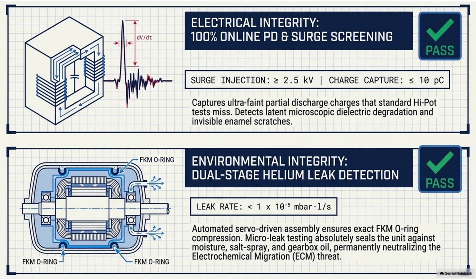By the time that wave reaches the motor terminals, the filter has squashed the violent vertical spike into a gentle slope, bringing the dVdt stress down from 10 kilovolts per microsecond to under 1.5 kilovolts per microsecond. It is like putting a massive shock absorber between a sledgehammer and a piece of glass. You basically eliminate the wave reflection and the impedance mismatch at the motor. You do? The overstress condition required to trigger partial discharge just ceases to exist. That is deeply satisfying engineering.